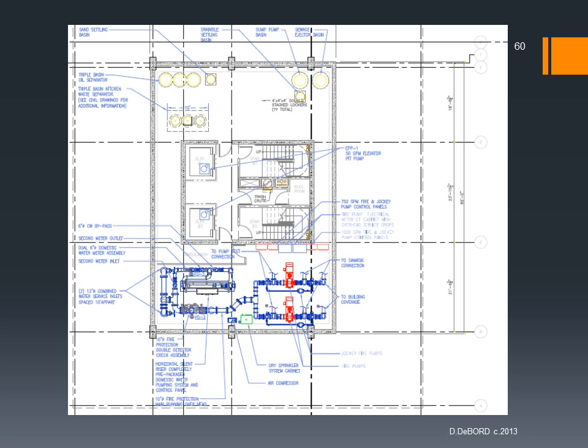We started off with the biggest because we were trying to get space. And that's common, especially in high-rise buildings. You've got to try to get the space because they're never going to want to give it to you anyway. And these are split case horizontal pumps, so they take up more room. And you can see we're taking up that whole lower right hand corner. You need to have 3 foot clearance in front of the controls, the control panels. So then we devised another scenario with going with vertical turbines, and they cost more, but it's easier to install and they take up less space. And we're not really talking about fire protection in this class, so we'll just leave it at that.